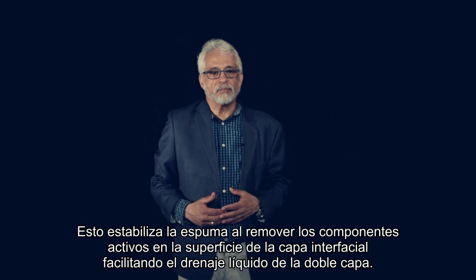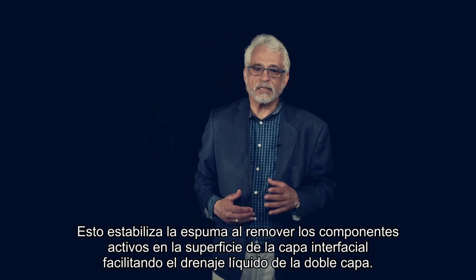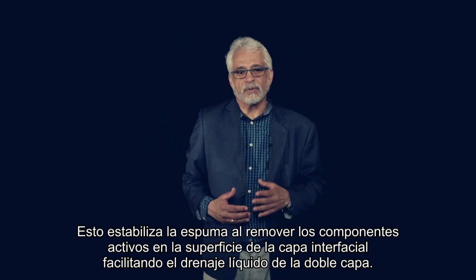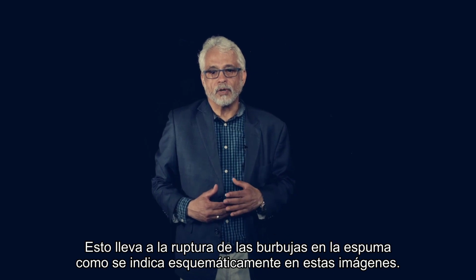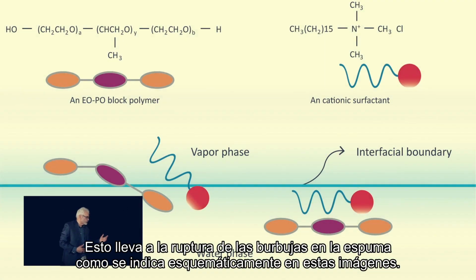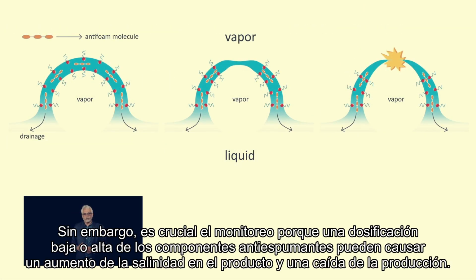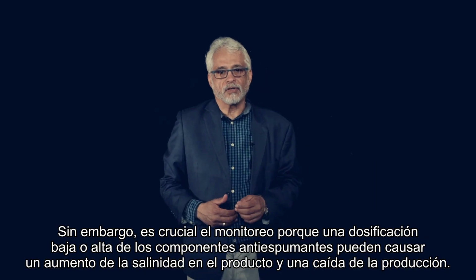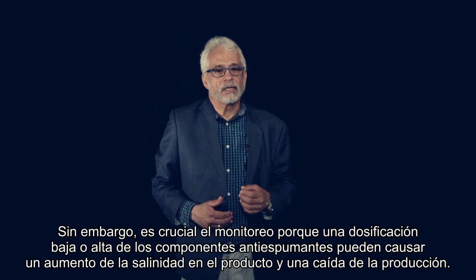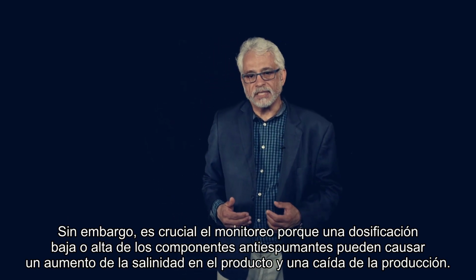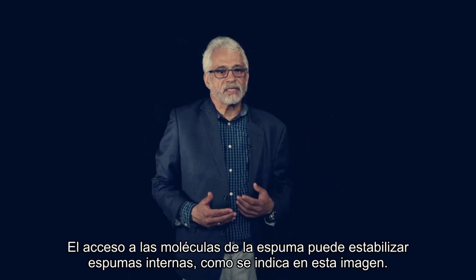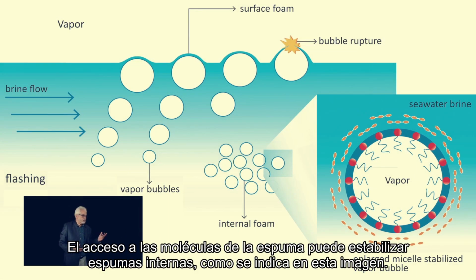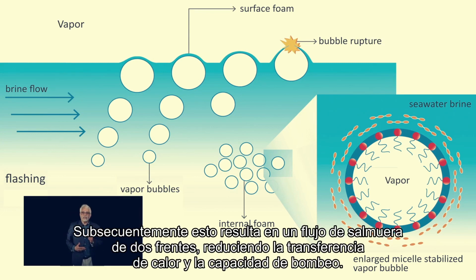It destabilizes foam by removal of surface active components from the interfacial layer, facilitating liquid drainage of the double layer. This leads to thinning and rupture of the foam bubbles, as schematically indicated in these pictures. However, monitoring is very crucial because under- and overdosing of the antifoam can cause increased product salinity and production decay. Excess foaming molecules may stabilize internal foams, as illustrated in this picture. Subsequently, this results in a two-phase recirculating brine flow, reducing heat transfer and pumping capacity.